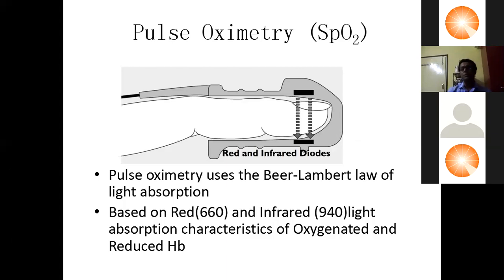There are two types of probe. One is the transmission type, where one side has a transmitter and the other side has a receptor. The other is the reflective type, where both are placed on the same side. Transmitting probes are generally applied over the fingers, and can be applied over the earlobes, and in newborns over the heels. Studies have shown that changes in SpO2 can be caught more quickly at the earlobe than at the fingers. Reflective probes can be applied on flat surfaces like the forehead and the chest.